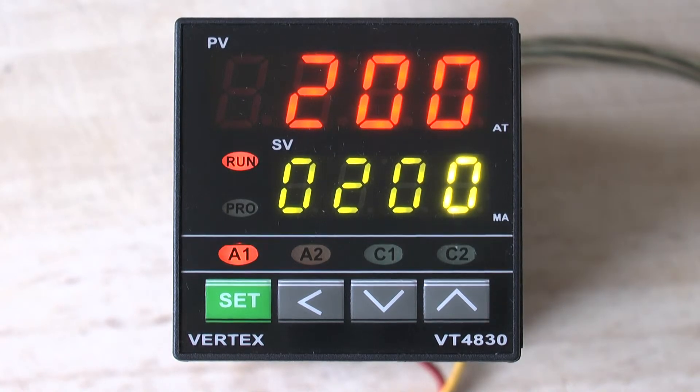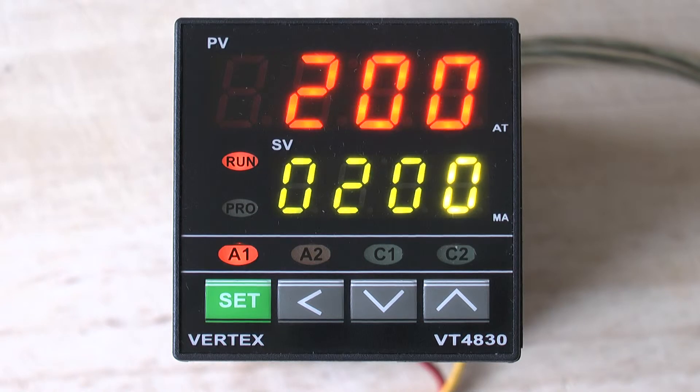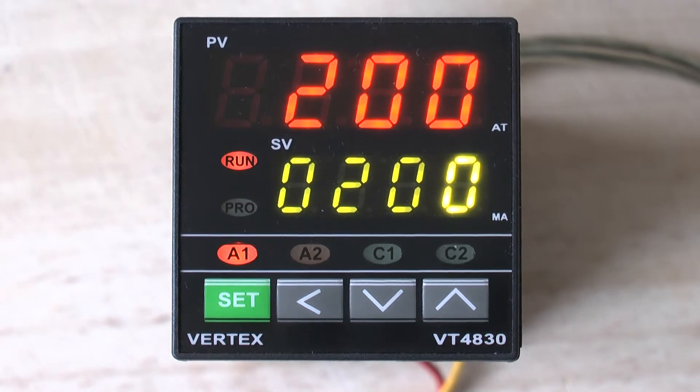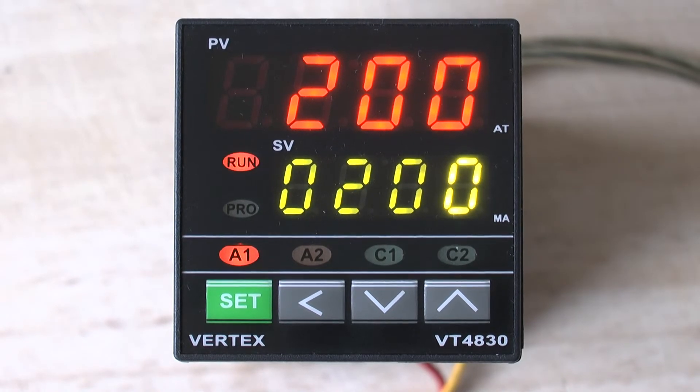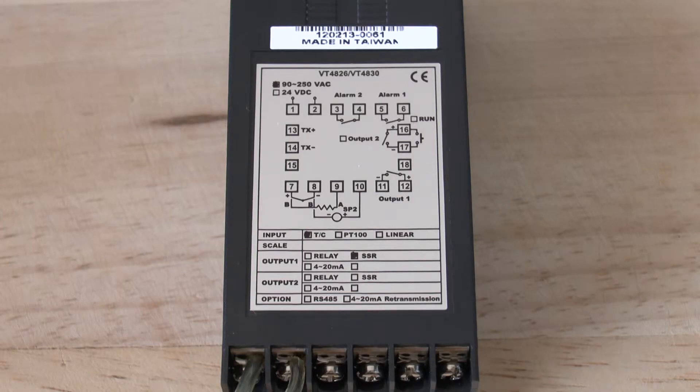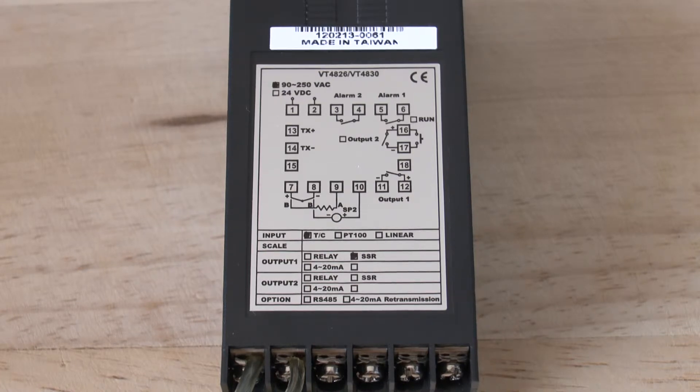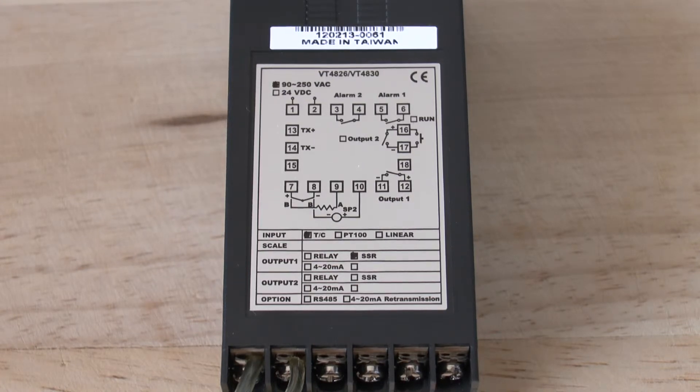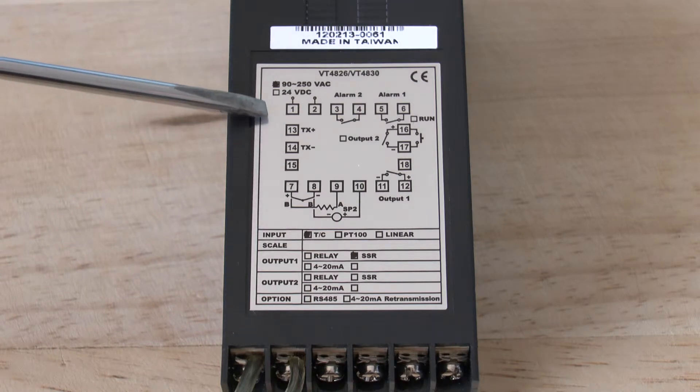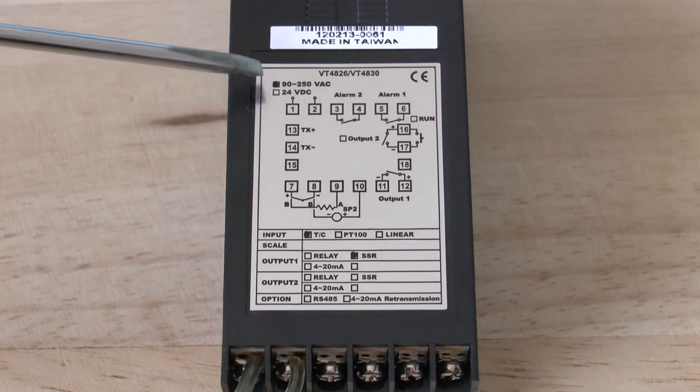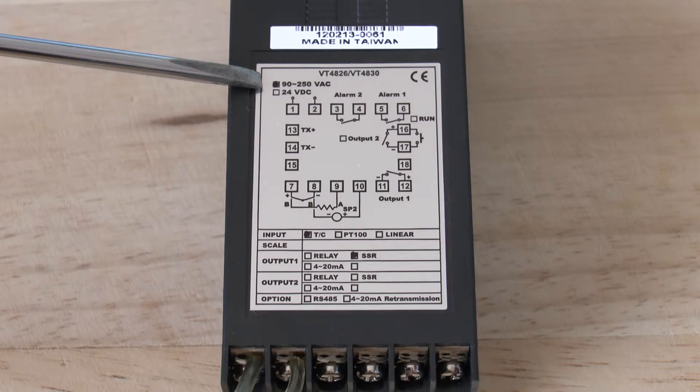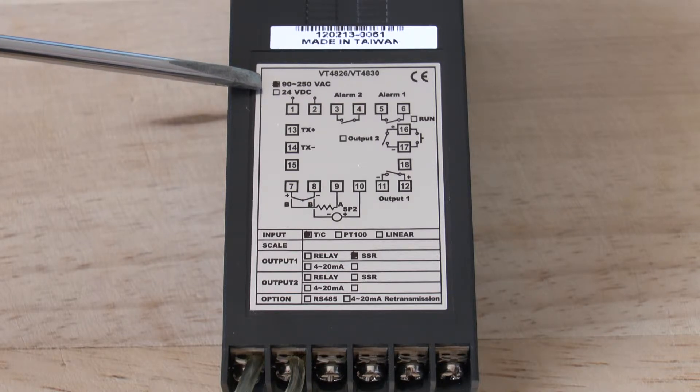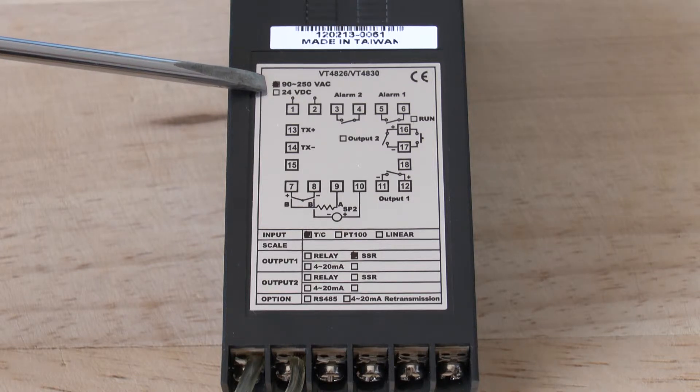Thank you for buying our new Vertex VT4830 controller. On the Vertex VT4826 and VT4830, the mains wiring goes on terminals 1 and 2. You will notice the little block has been colored in, indicating that this particular unit works on a voltage between 90 and 250 volts.